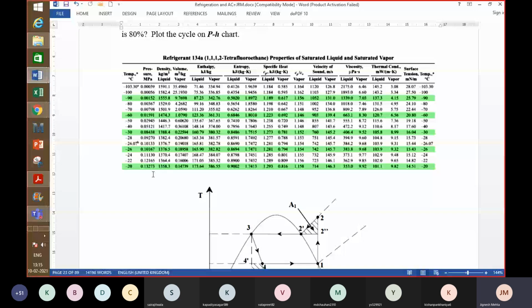What you measure with gauges are the gauge pressures, right? So when you want to use the tables, in case you are measuring the parameter with a gauge and then trying to refer to them, you should add whatever is the ambient pressure before referring to the table.